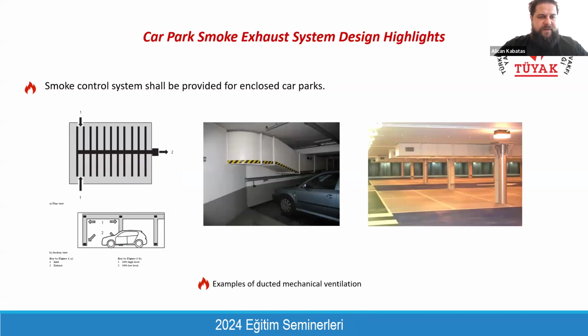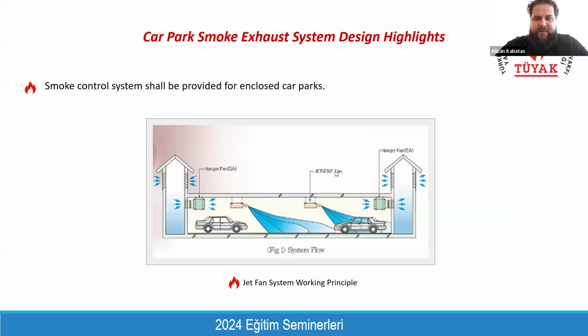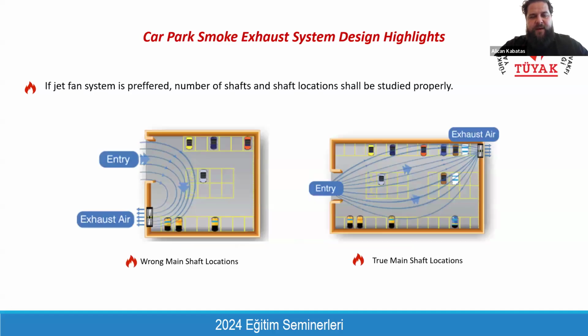There are different types of smoke extraction systems. There are ducted types of smoke extraction system. There are jet fan systems, and you can see here a ducted type of smoke extraction system, but it is taking a lot of space from the floor height. And as you know, due to investment issues, the height of car park levels is tried to be kept to a minimum. That's why nowadays you cannot see a lot of these ducted systems. Instead, they are using these jet fan systems. Jet fan systems are standalone fans, and they do not cause a loss of floor height. That's why they are preferred, and you can ask the mechanical designer to take the floor height limitations into account and to provide a jet fan system.